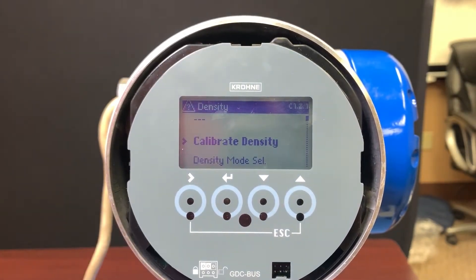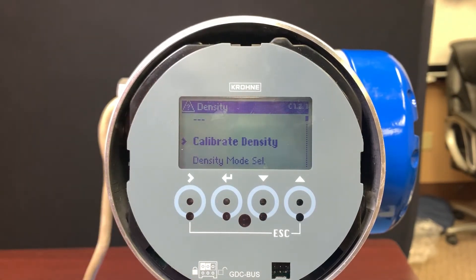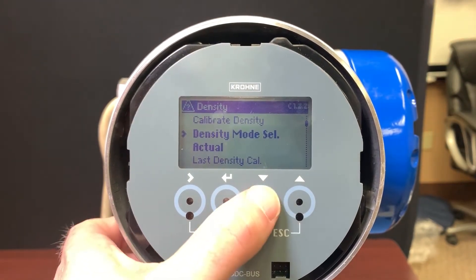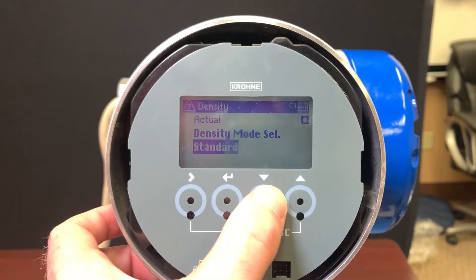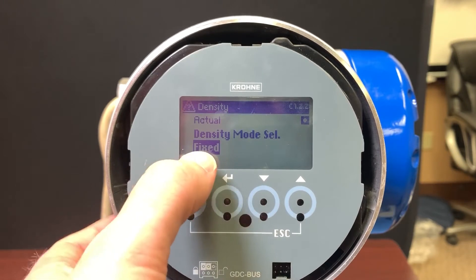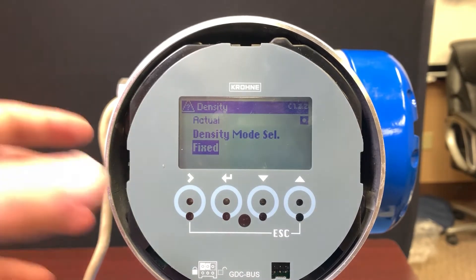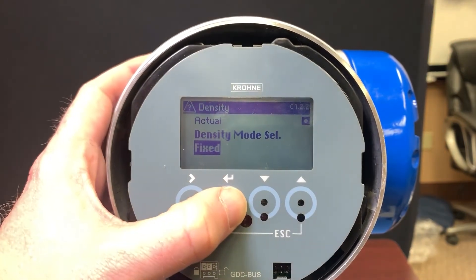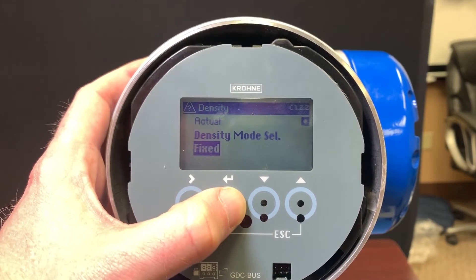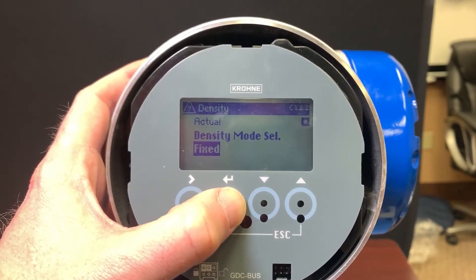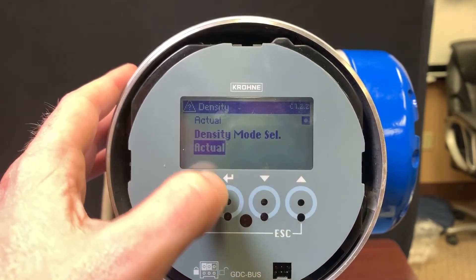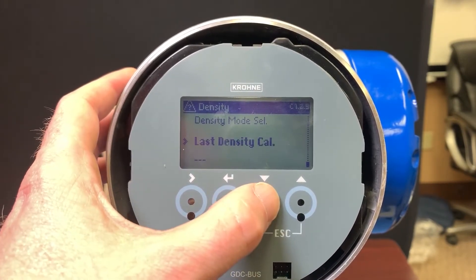Density — if you have a particular product and you know the density and you're seeing a deviation, and you want to do a calibration for density, you can do that. There are quite a few different calibration density modes. I want to highlight the fixed one, because what that allows you to do is basically assume a steady density no matter what passes through. That can be valuable if you're having some slight gas entrainment and don't want to see volume swings, though there are some implications if you leave that in place. We're going to stay on actual and go from there.